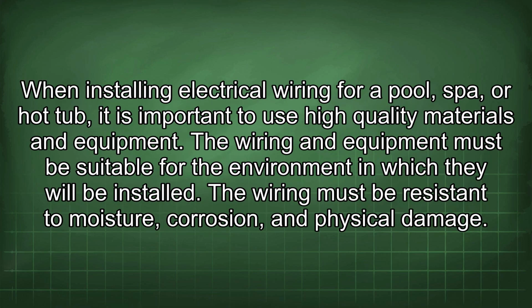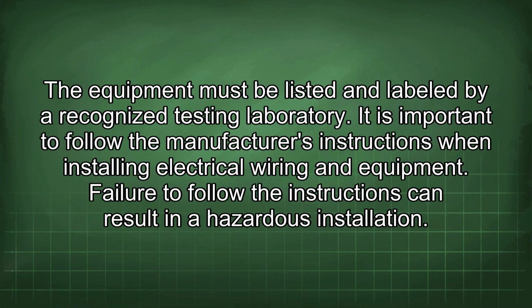When installing electrical wiring for a pool, spa, or hot tub, it is important to use high-quality materials and equipment. The wiring and equipment must be suitable for the environment in which they will be installed. The wiring must be resistant to moisture, corrosion, and physical damage. The equipment must be listed and labeled by a recognized testing laboratory. It is important to follow the manufacturer's instructions when installing electrical wiring and equipment. Failure to follow the instructions can result in a hazardous installation.